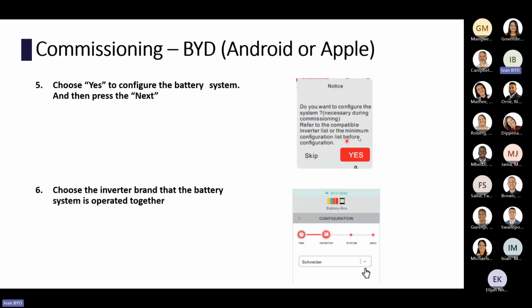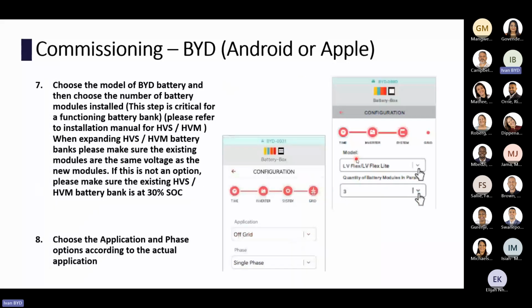And if you're configuring the system, you just say, yes, I want to configure the system, and then you synchronize the time, and then you choose the inverter. This is more for record keeping. The most important step is selecting the right model of battery and selecting the right number of battery modules. Those are very important steps.